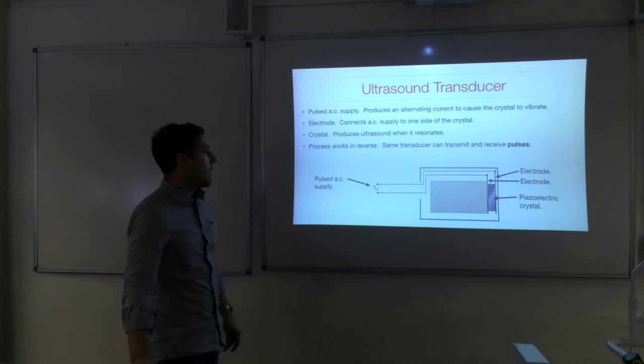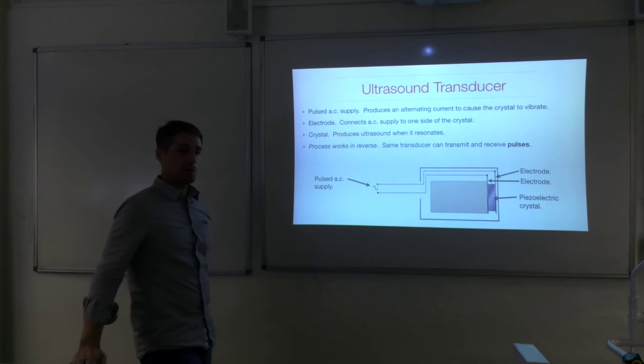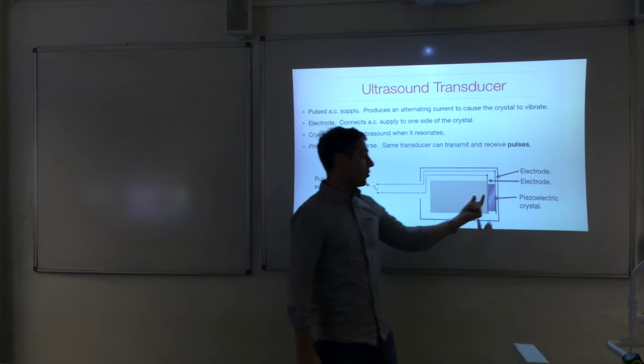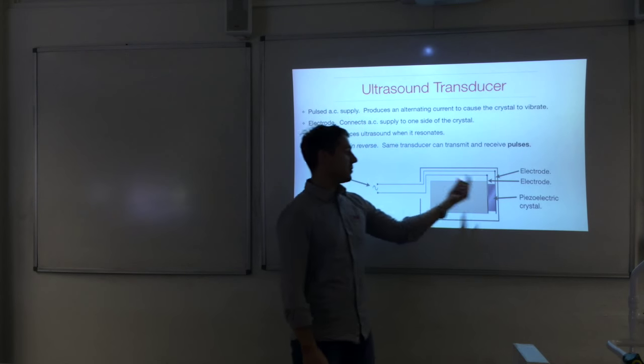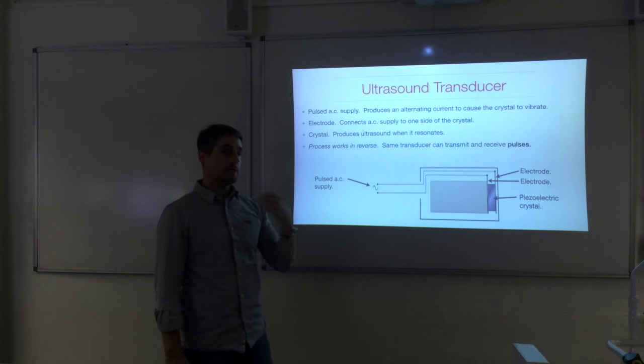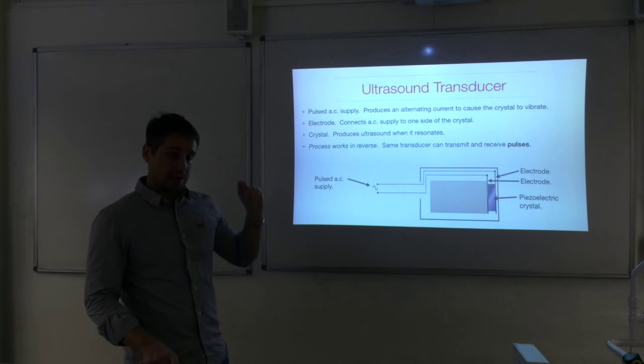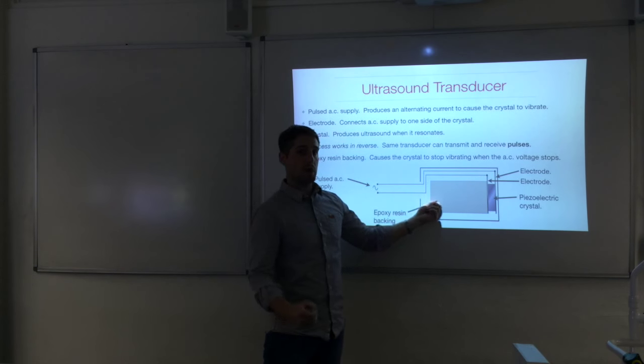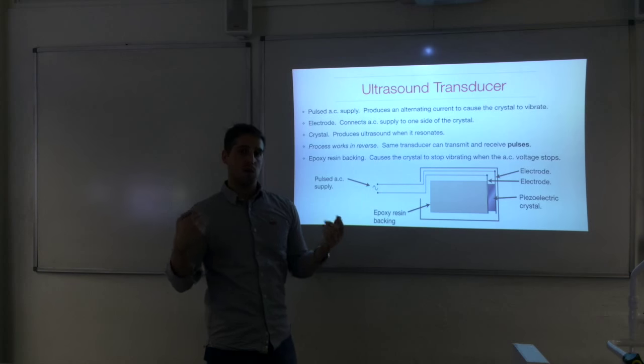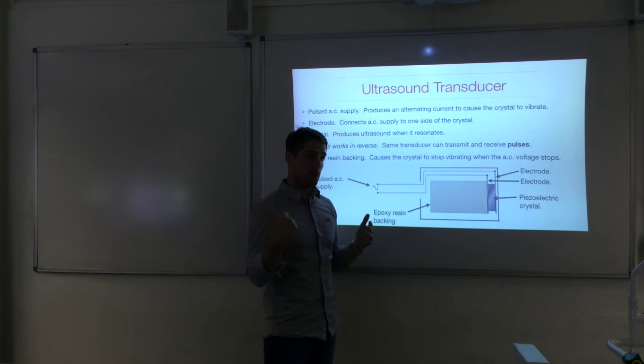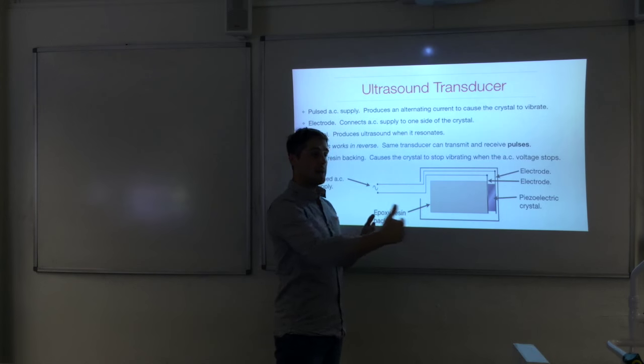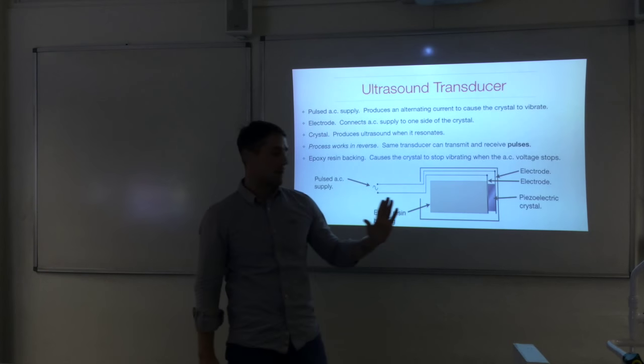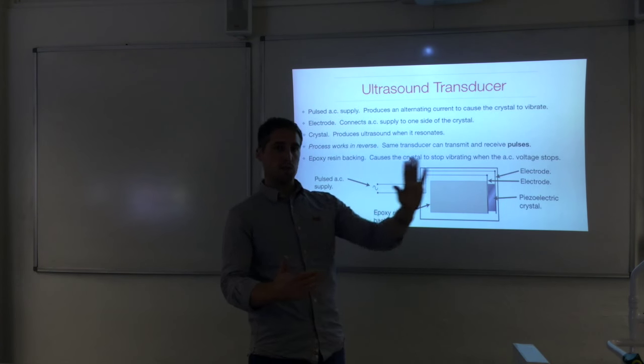This process works in reverse too: if ultrasound is incident on the piezoelectric crystal it causes it to resonate, producing an alternating potential difference across the crystal that can be received. This means you can use exactly the same transducer as both transmitter and receiver. The epoxy resin backing prevents the crystal from continuing to vibrate when you want to switch to receiving mode. Ultrasound transducers produce impulses — they transmit a pulse and then receive.